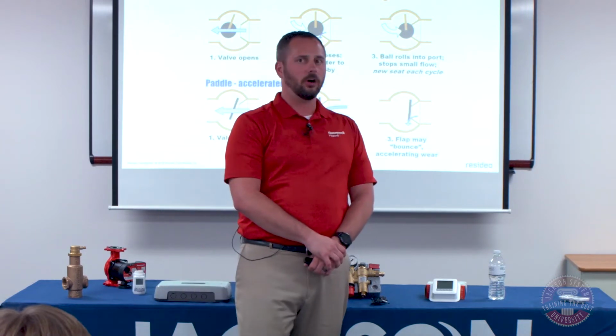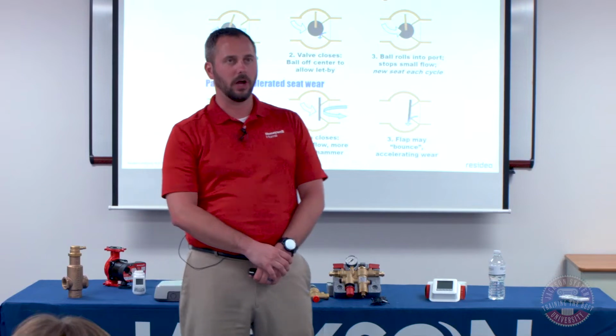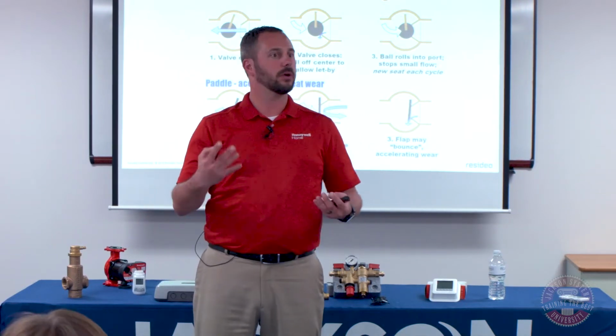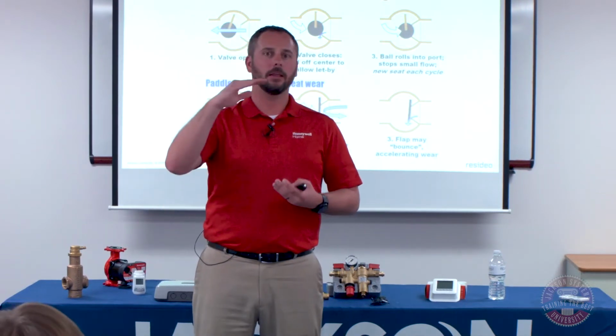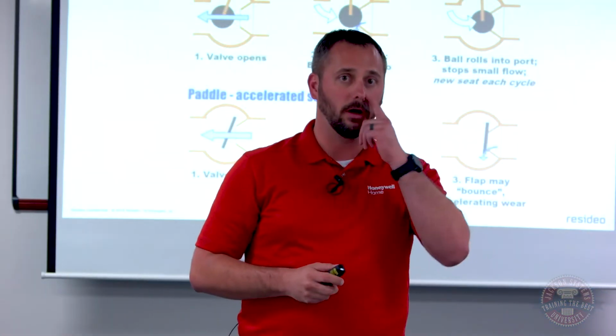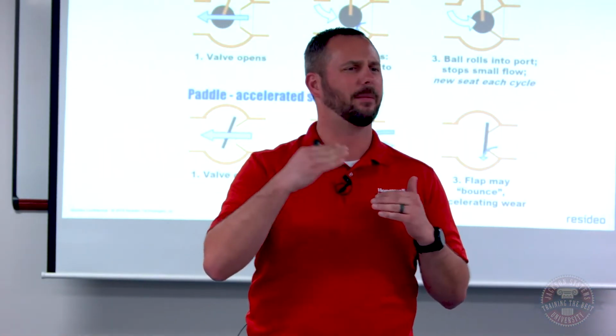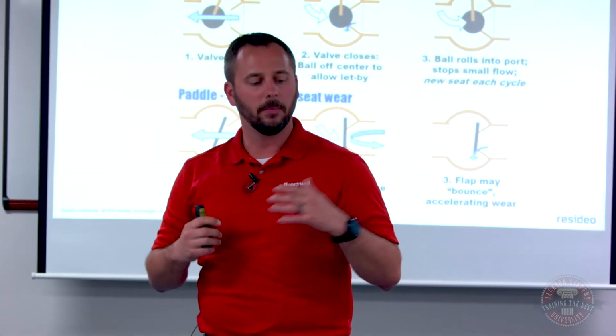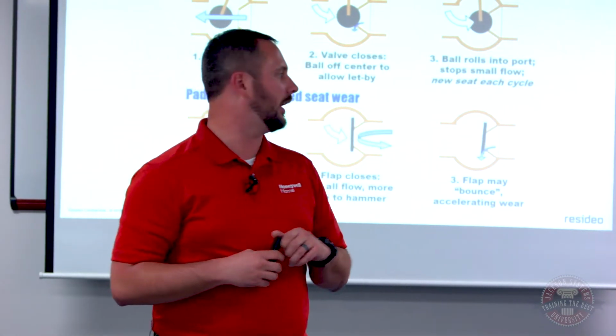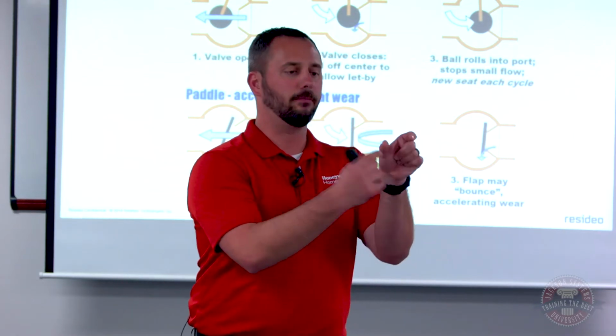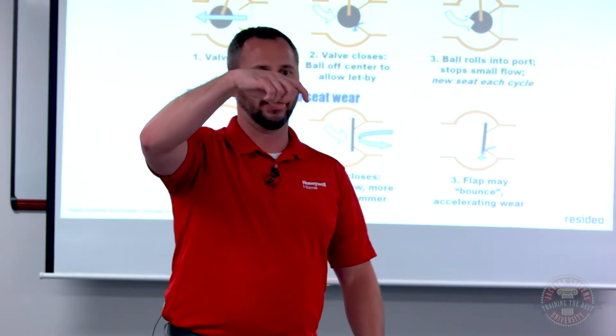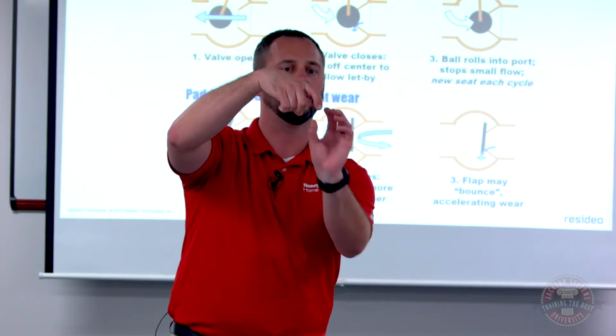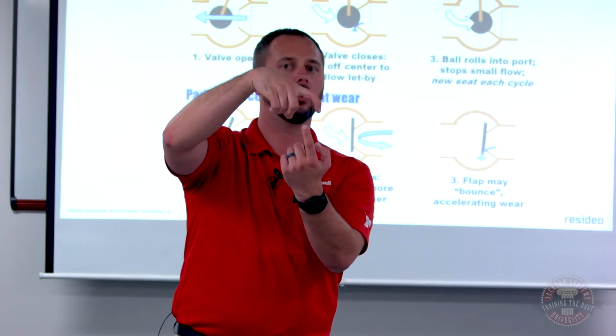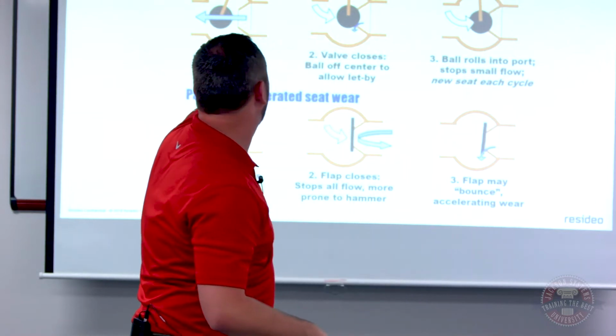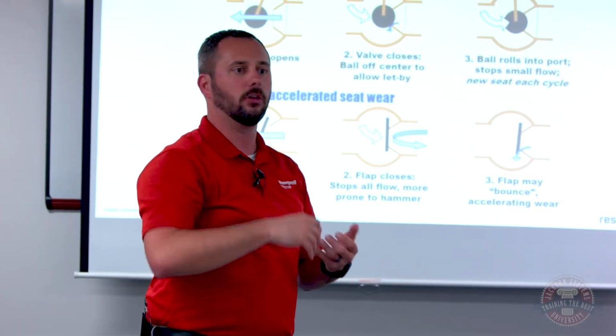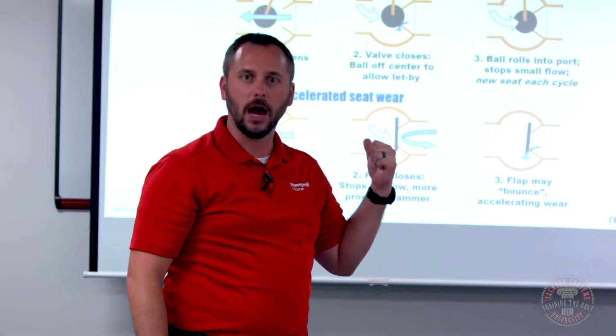As I had mentioned in our zone valve series, when we were talking earlier about valves that have 3 wires, you can open it and close it, that's a different style of device. That's more of a globe valve actuator, more of a piston style than this series. But in this series, we have this ball inside of here, and I wish I had a cross section to show you. This ball basically sits on a little spindle. That spindle is what opens and closes. That ball will actually twist inside of there. So every time it closes, it's closing in a different spot. So the longevity of the guts of this thing is absolutely phenomenal.